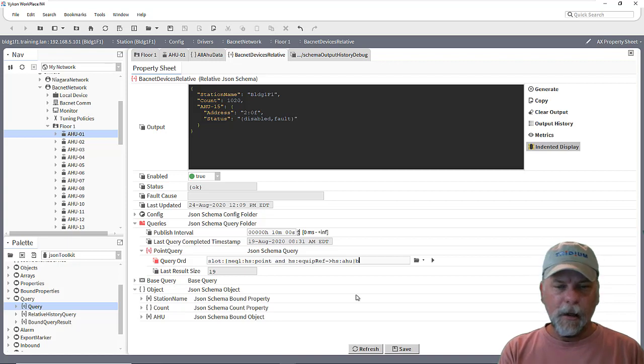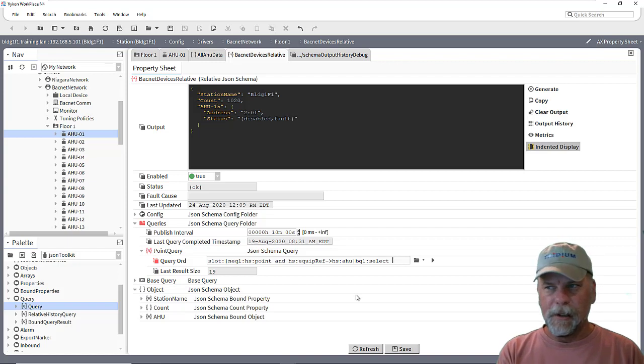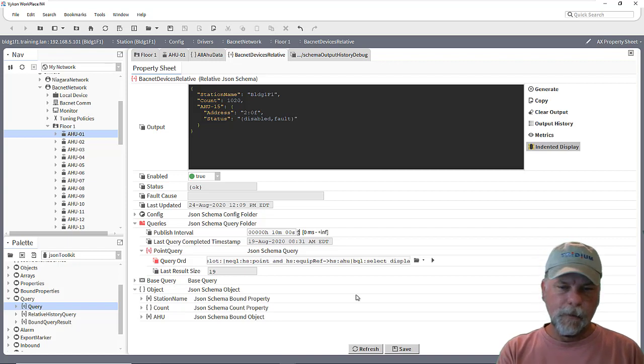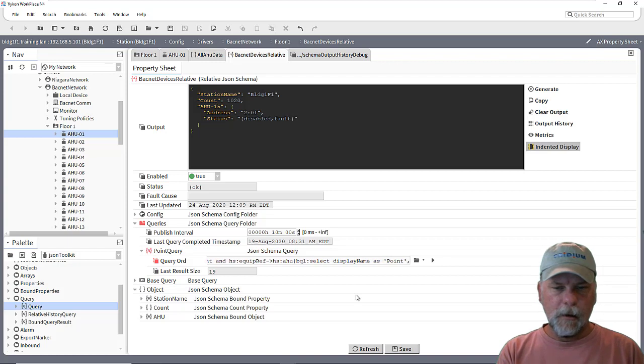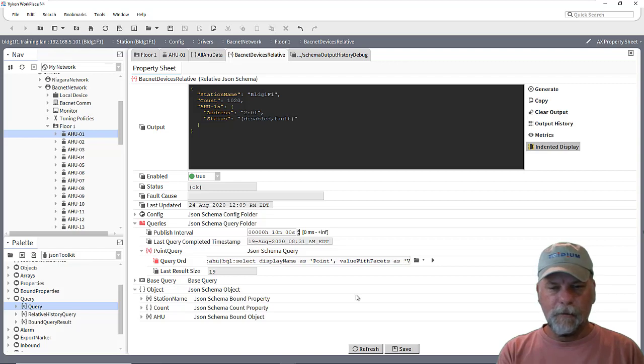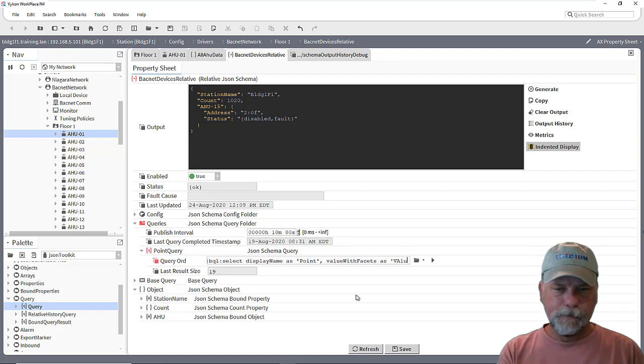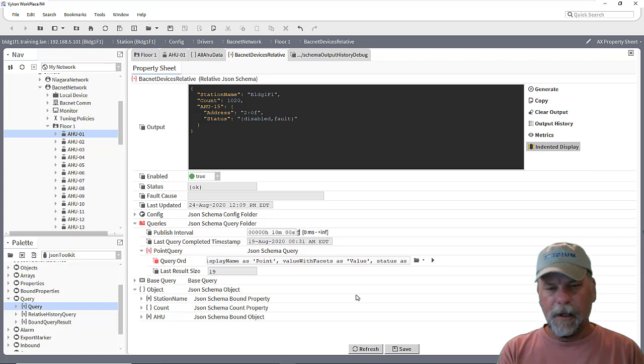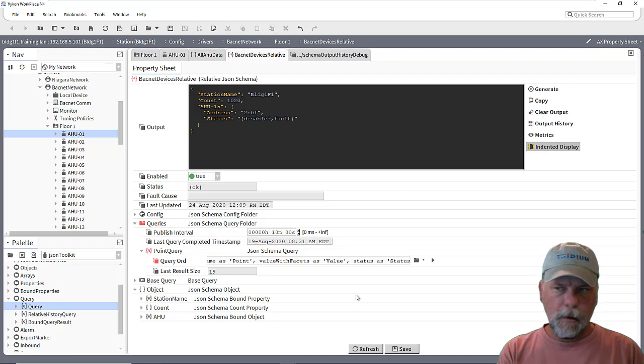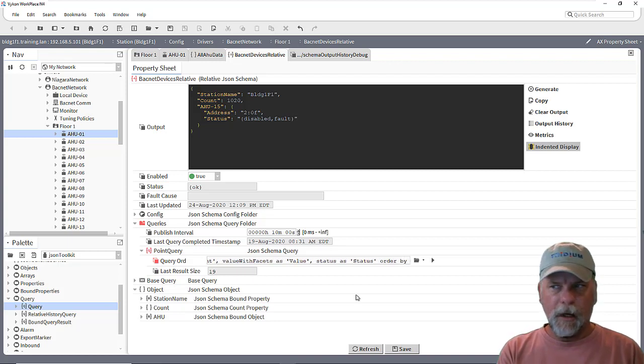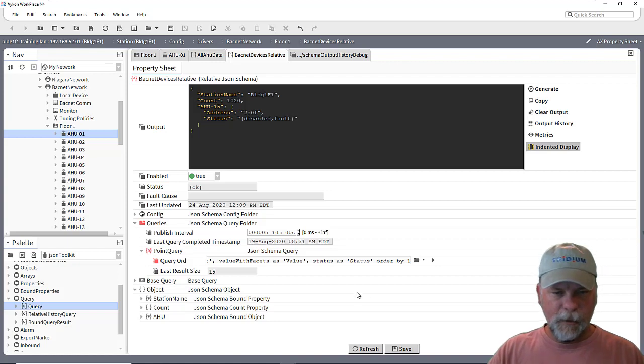But anyway then we'll do a BQL query to specify the projection here. So we'll say display name as point and then value with facets as value. And if I really want, status as status. And then we can order by the first column which is the name of the points.